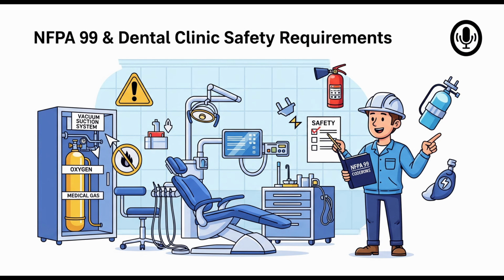Right. Electricity is covered in Chapter 6. And just like with the gas systems, the requirements are tiered based on the risk category. For a facility operating mainly at Category 3, the code points towards Section 6.6 for specific requirements, and it also heavily references NFPA 70, which is the National Electrical Code, or NEC. So NFPA 99 and the NEC work together here. They do. Now, the most direct mentions of mandatory emergency power for Category 3 systems in the source text relate back to the systems we just discussed.